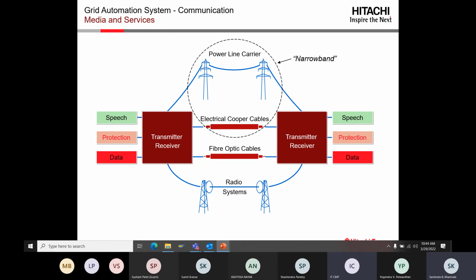Within a substation communication, say within one building, we use multi-mode cable, but between substations we use single mode fiber optic cable, as each has its own advantages and disadvantages. Single mode fiber has the advantage of lower attenuation on the transmission of optical signal, but it is costlier. Multi-mode fiber is less costly, but has more attenuation to the optical signal. So we use multi-mode fiber within a substation, connecting two different switches or devices in one building.